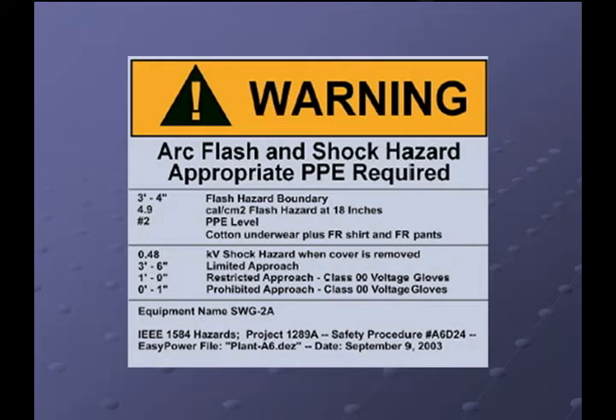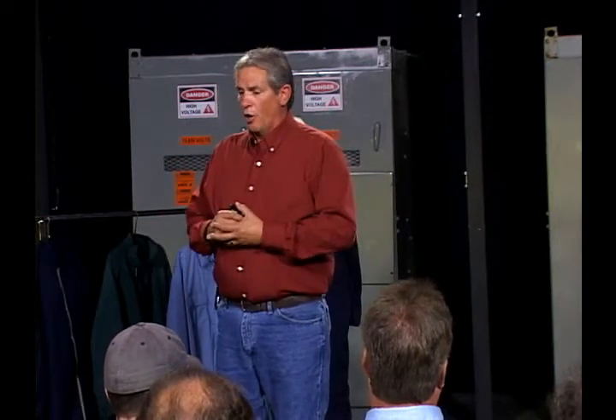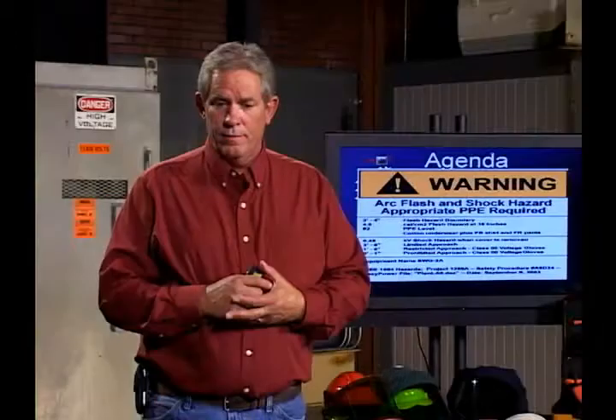In this case, it's 3 feet 4 inches, and that is not a safe boundary. Let me repeat that — that is not a safe boundary. What that means is if I'm standing 3 feet 4 inches away and an arc flash occurs on a piece of equipment, I could still receive a 2nd-degree burn on unprotected skin.